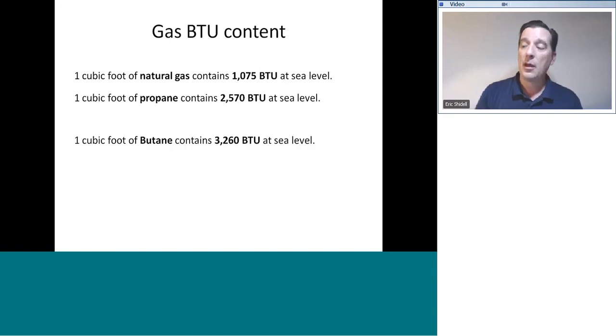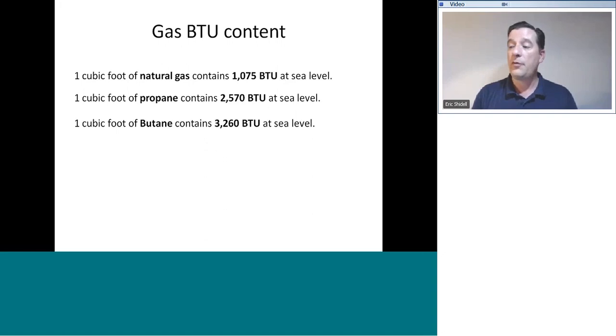Good to know. We'll talk a little bit more about that when we get more deeply into the propane side of things. Butane, by comparison, 1 cubic foot of butane contains 3,260 BTU at sea level. So about 3,200. Check that out between propane and natural gas. Remember, we're not really too worried about butane, but propane and natural gas, propane has about 2.5 times the heat content per cubic foot that natural gas does. It's significantly more BTU per cubic foot than natural gas does.